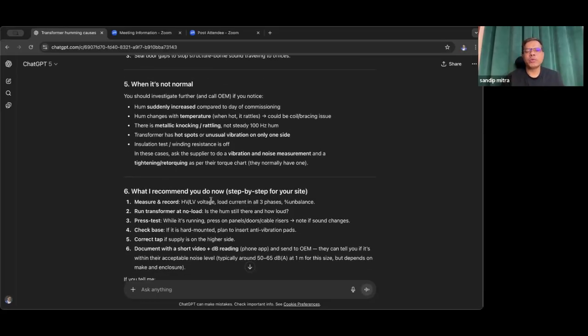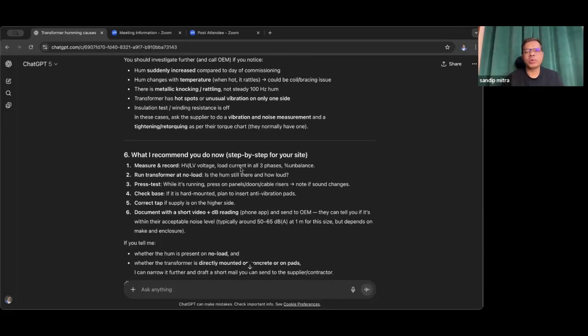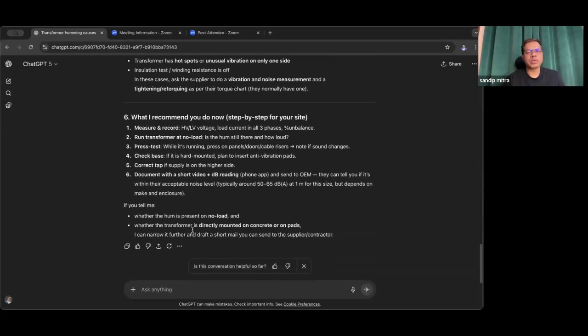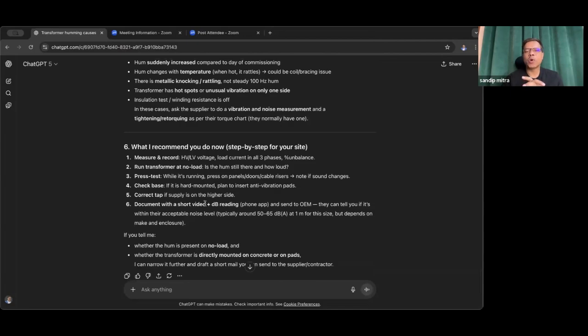So what I recommend you do now, step by step for your site. Number one, measure and record HV and LV voltage and load current in all three phases. If you have all the equipment, you can do that by yourself, or you can call the OEM to execute all those things. Run the transformer at no load, check the base, check the correct tap, and document with a short video plus a dB reading, a decibel reading from a phone app, and send it to the OEM. They can tell you if it is within their acceptable noise level, typically around 50 to 65 decibels at around 1 meter for this size, but it depends on make and enclosure. So that way, at least you can understand what the problems are.